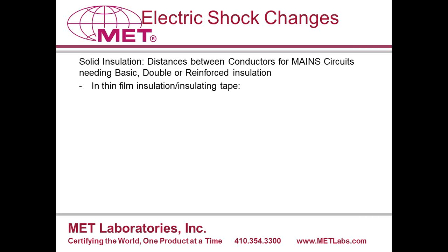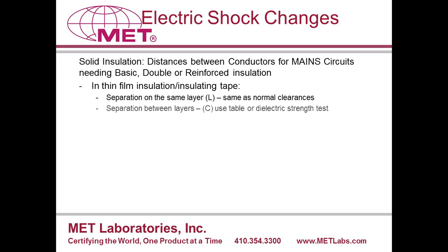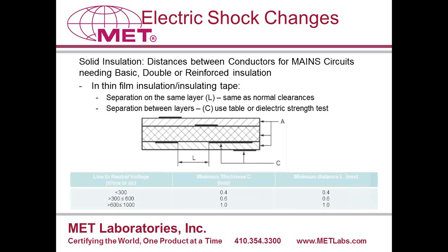For thin films, the separation between conductors on the same layer is the same as clearance values in air, but between layers it is treated the same as a circuit board. Insulation tape is treated as a thin film. However, since it's almost always less than 0.4 millimeters, dielectric strength testing is required.